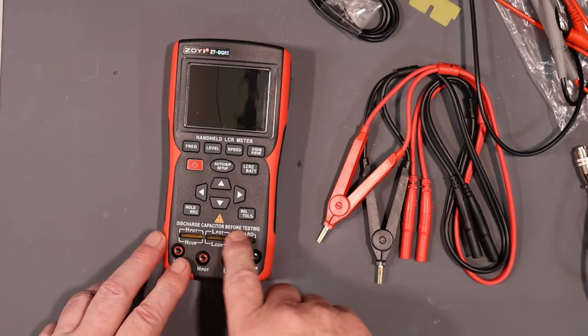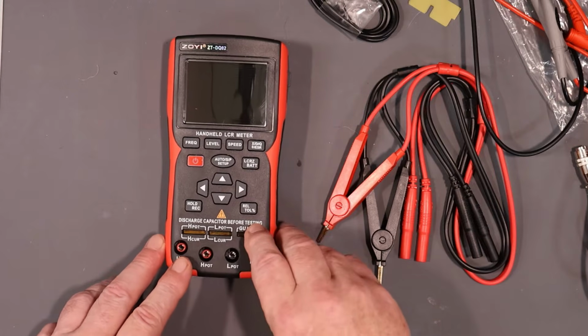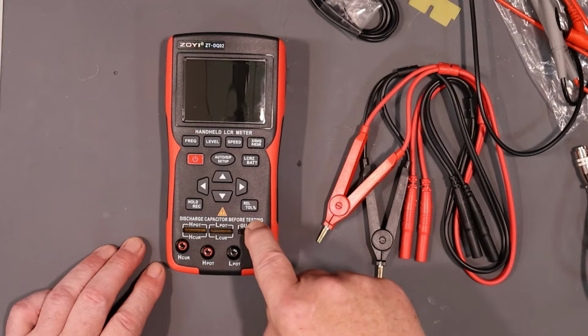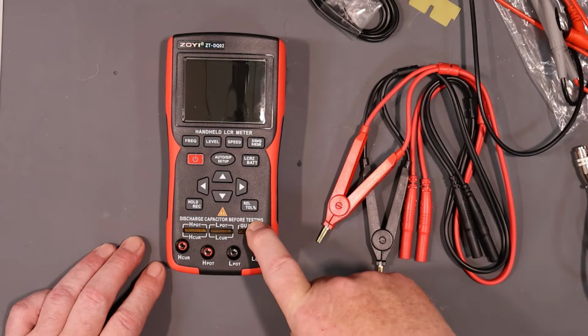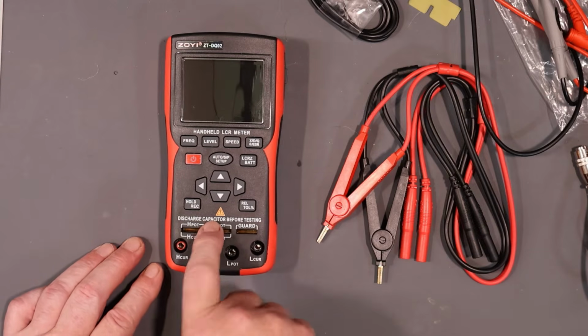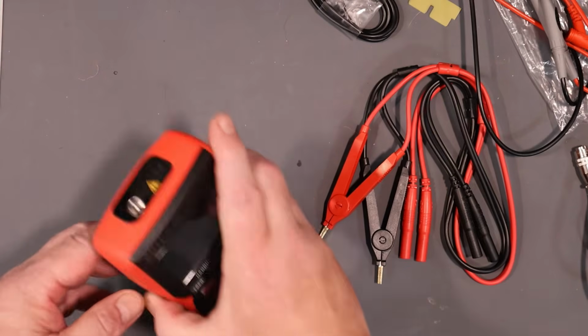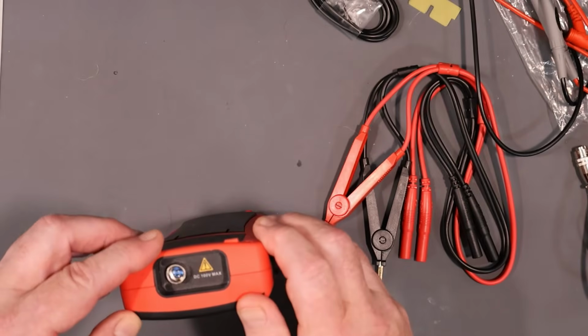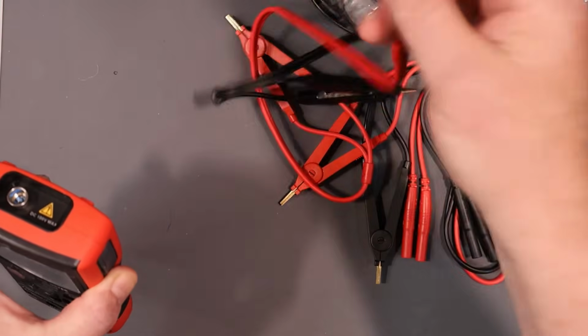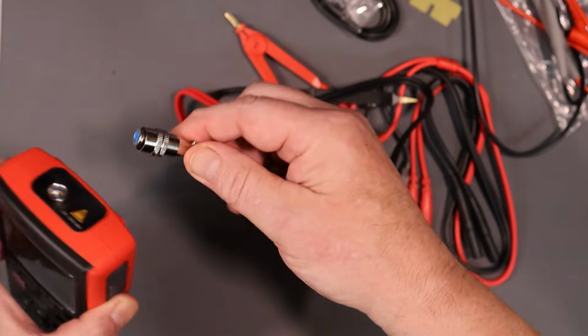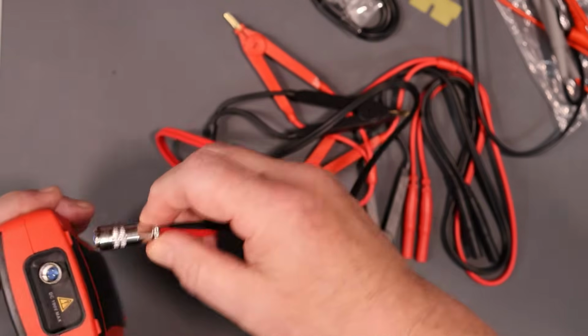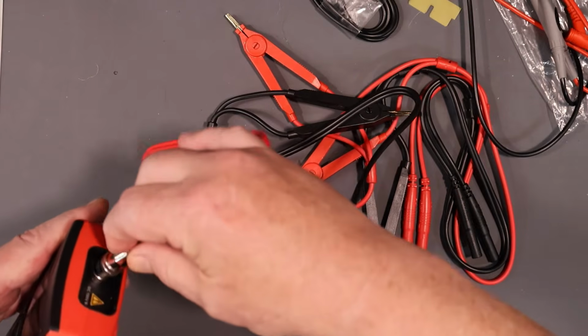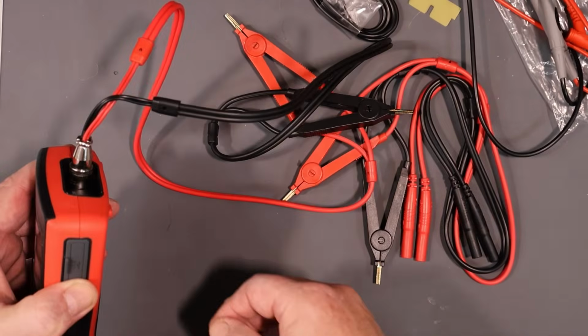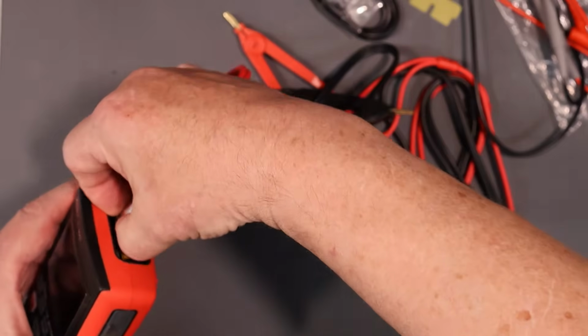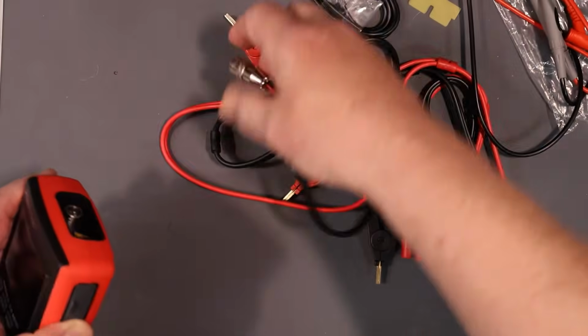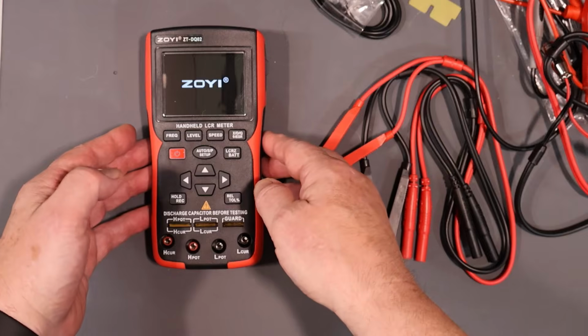It says here, discharge capacitors before testing. That's a really good idea, just in case you take a capacitor out of a power supply and you want to check it out and it's got like 60 volts across it. This wouldn't like that very much. And up here we've got this special connector here for the internal resistance tester. It's one of these aviation type things where you just push it into place once you get it oriented properly, and it snaps in like that. So you don't have to do anything, and then to remove it you pull the ring up and it'll pop out. Okay, so let's turn it on.